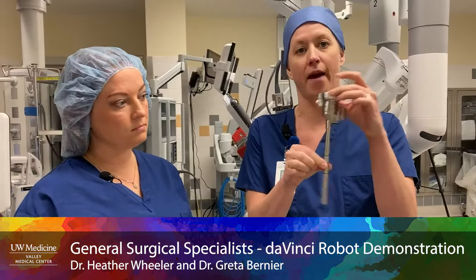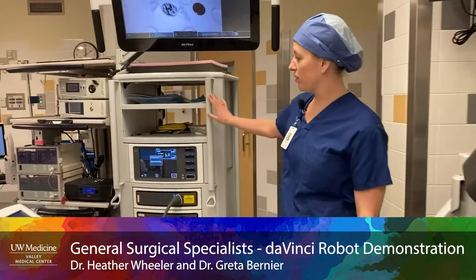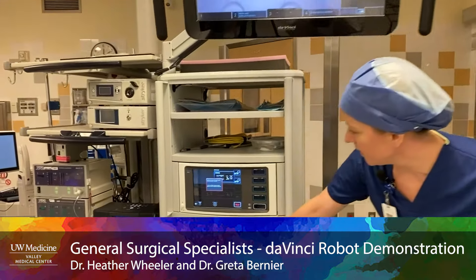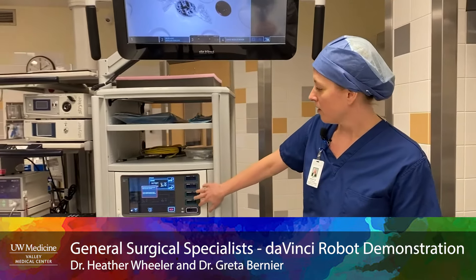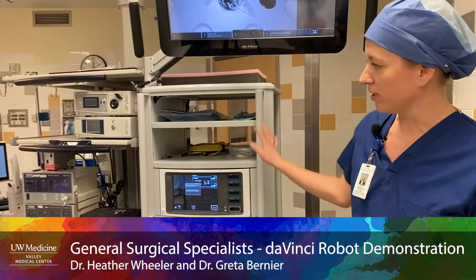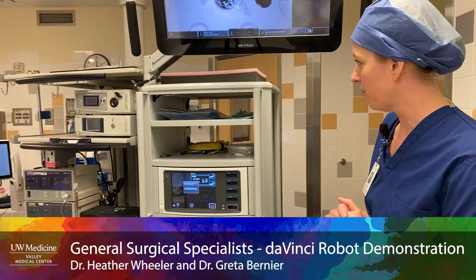And this is the vision cart, or some people call it the energy cart — this is what has all the components. Our camera plugs in here, our energy devices plug in here. If we need to use cautery or any other kind of advanced energy devices, those all go in here. And then this is usually side by side with the other equipment that we need to fill the belly with carbon dioxide and whatnot.